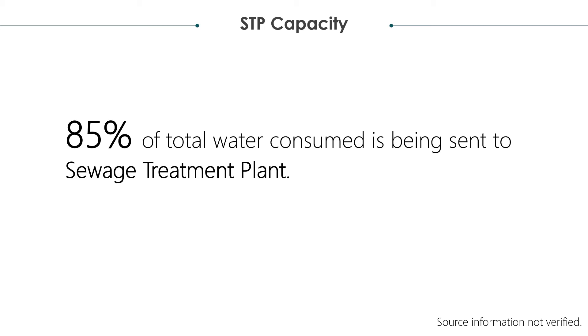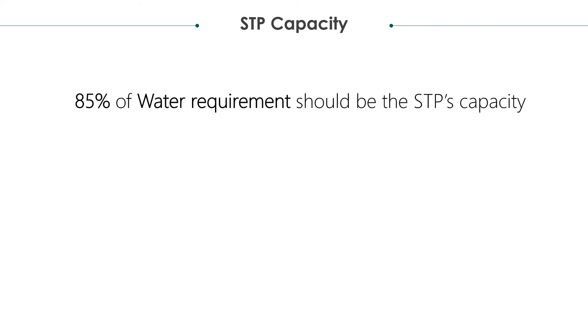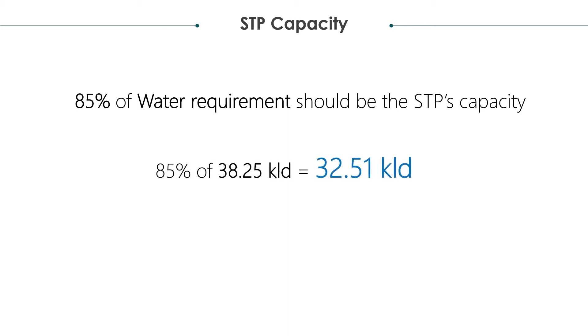Therefore, 85% of total water consumed is being sent to the sewage treatment plant. Hence, 85% of the water requirement will be the STP capacity. 85% of 38.25 kiloliters per day is equal to 32.51 kiloliters per day.